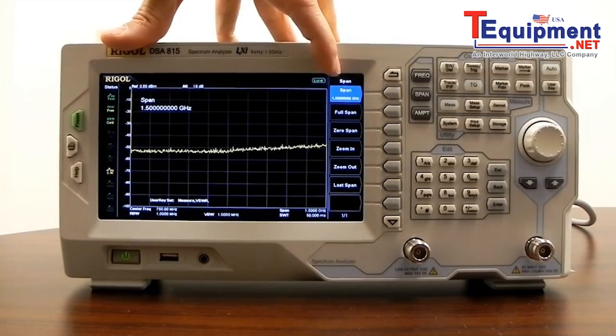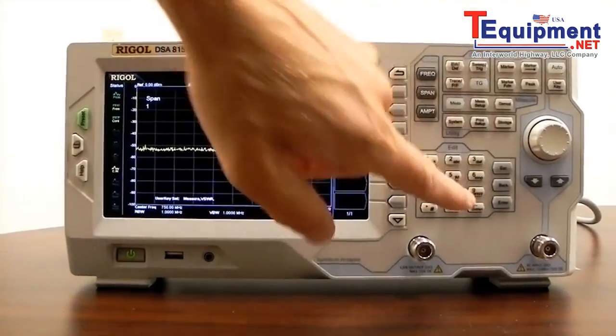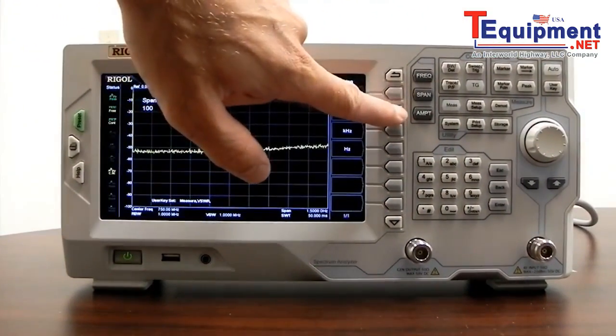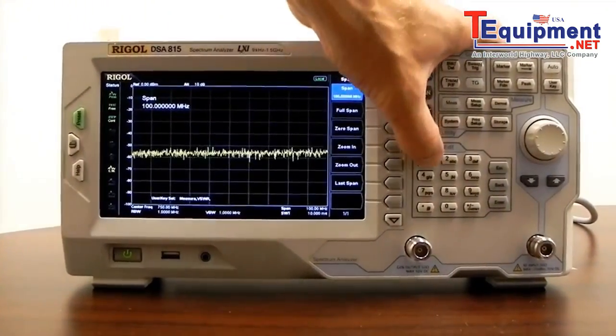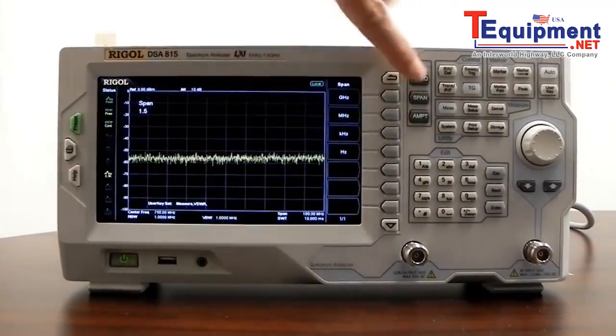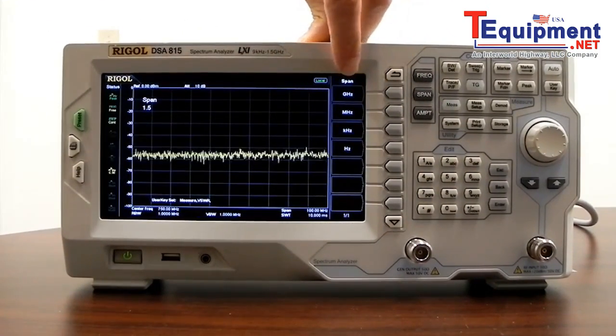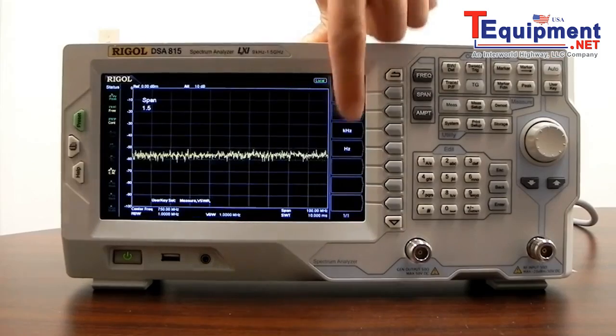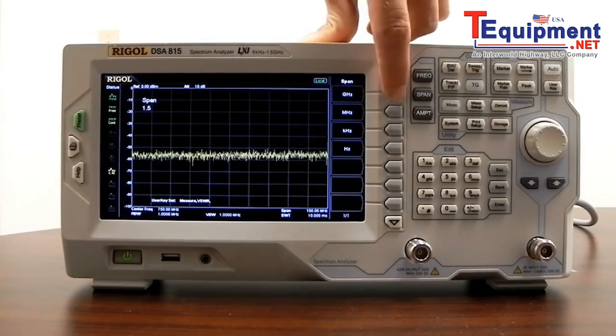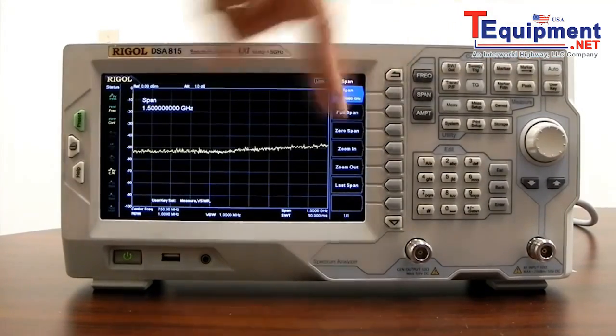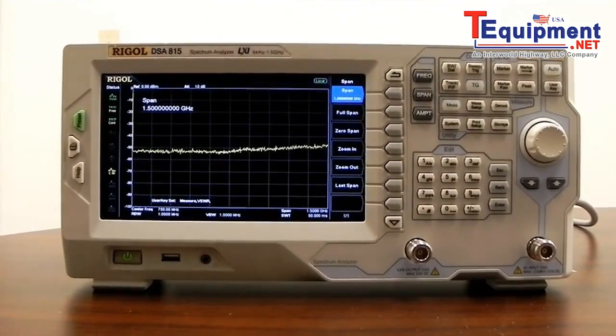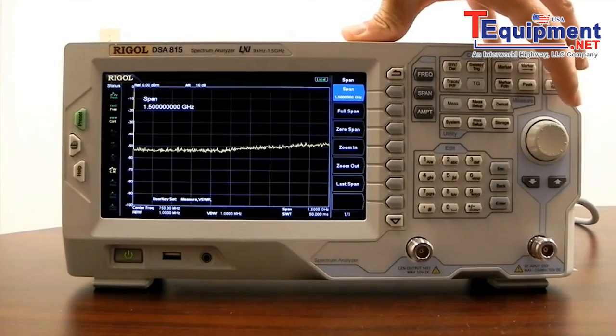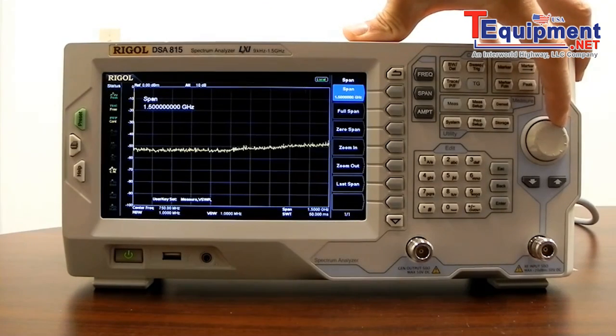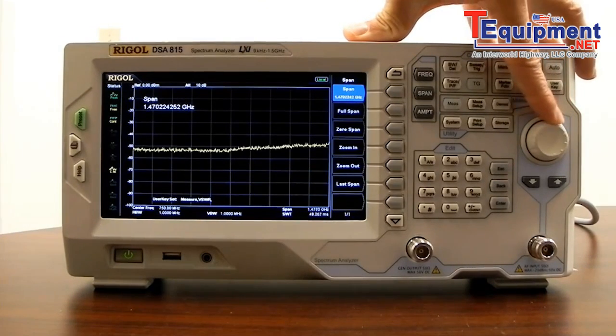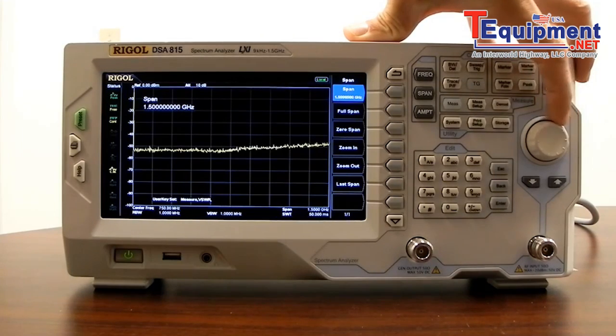I'm sorry, 1.5 gig. If we wanted to change that, we could go to 100 and press megahertz, or we could go back to 1.5 and press gig. Again, on this particular instrument, we have the ability to just enter directly in units, which is really nice, because instead of having to put 1.5 and a whole lot of zeros afterwards to get gigahertz, we can just select units. Or we can use the scroll wheel if we just want to change a few values or change them in smaller increments.